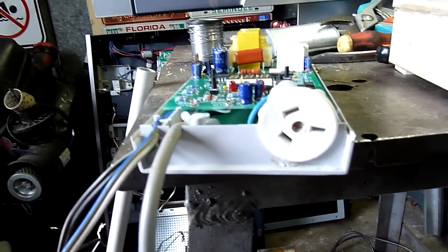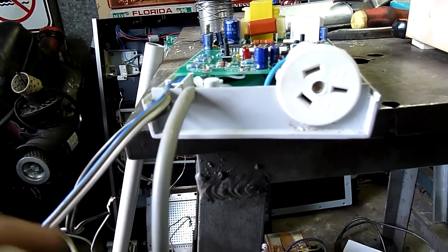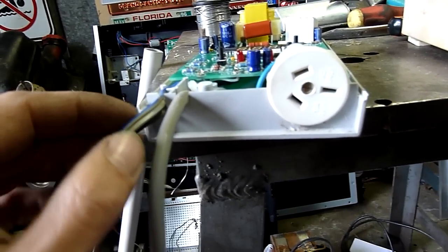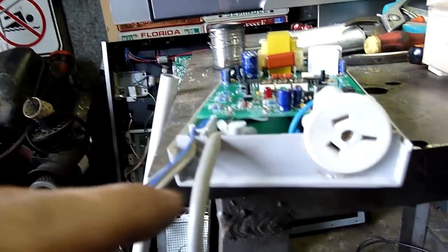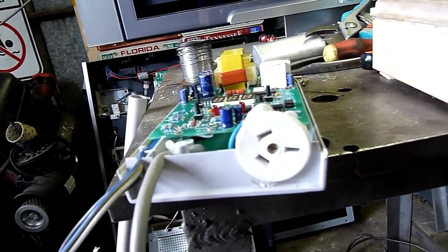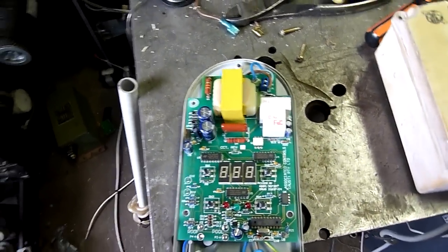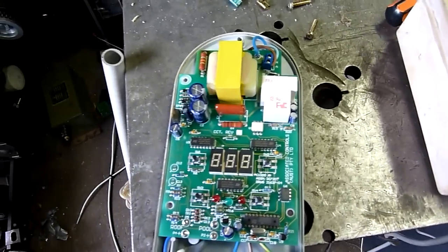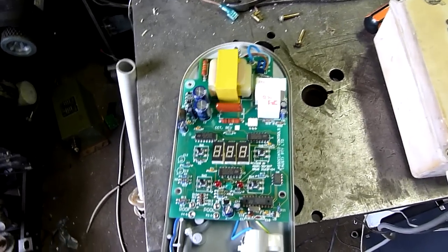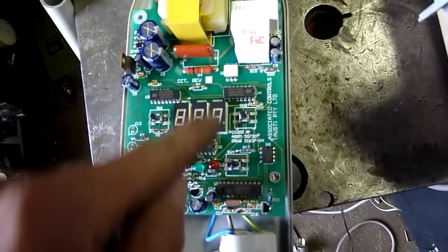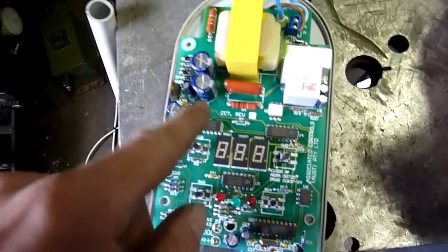I notice the cable reliefs in here are fairly open, and one of the problems I have with the ones at work, as the pretty much dedicated repair technician now, I find that ants and things get in there and make nests under the components and start shorting stuff out, particularly when they get into the switch mode power supplies. These old solid transformer-based ones aren't so bad, but the ones that run on switch mode power supplies do tend to die very quickly when you get ants between the legs of the opto-couplers and other things.